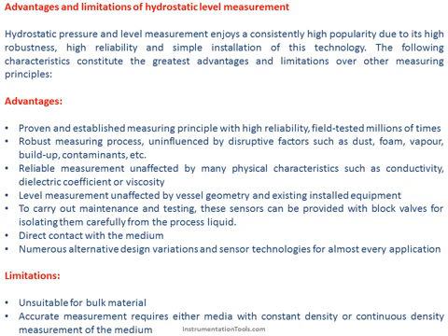Reliable measurement unaffected by many physical characteristics such as conductivity, dielectric coefficient or viscosity. Level measurement unaffected by vessel geometry and existing installed equipment. To carry out maintenance and testing, these sensors can be provided with block valves for isolating them carefully from the process liquid. Direct contact with the medium. Numerous alternative design variations and sensor technologies for almost every application.